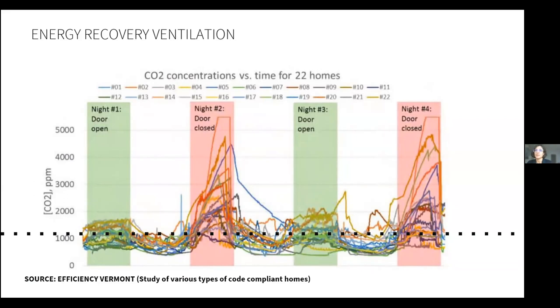The reality is, even with current requirements for energy code air tightness, if you are not providing dedicated fresh air that is balanced between supply and exhaust, the building is not achieving real air changes. There's much higher risk for condensation issues and for unhealthy air, which is not providing enough oxygen or flushing out toxins. Again, there are different ways to address this issue, and building codes are progressing towards mechanical ventilation being a requirement, just as sprinklers have become. Ventilation can be considered a life safety issue in many ways if you think about the implication on health. And Rachel will dive more into how her team addressed ventilation on Linden.